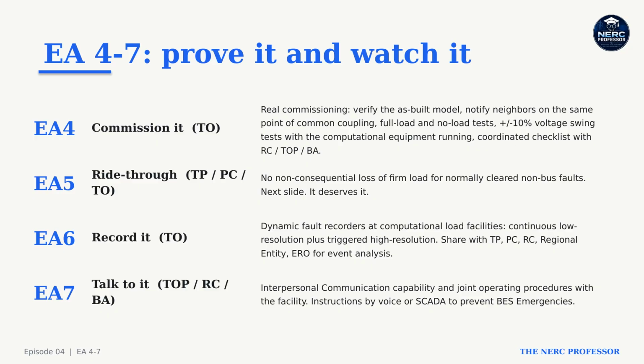Action 5, ride through. I'm giving that one its own slide. It deserves it. Action 6, recording. Transmission owners put dynamic fault recorders at these facilities. Continuous low-resolution recording plus triggered high-resolution recording. And they share that data up the chain for event analysis.